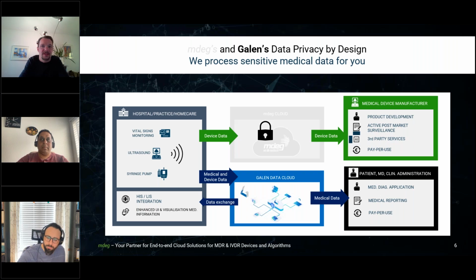they are really interested in the data from the device, like error messages or startup times, self-test reports, calibration data. This is what they are really interested in, and what they then use in turn to optimize their service. Usually they can easily decide if a device is broken and needs physical attendance. So the device is sent then to the manufacturer, or the service engineer goes to the clinic, or the technical service staff from the clinic can fix it. Maybe there is a replacement part necessary, so they can send it before they travel to the clinic.